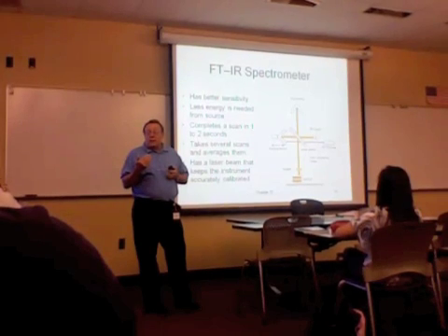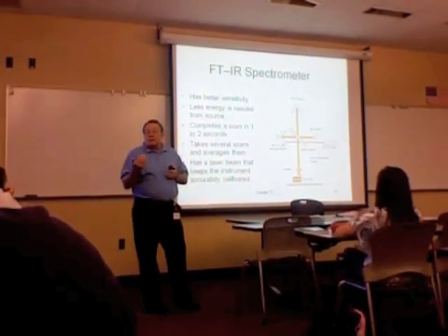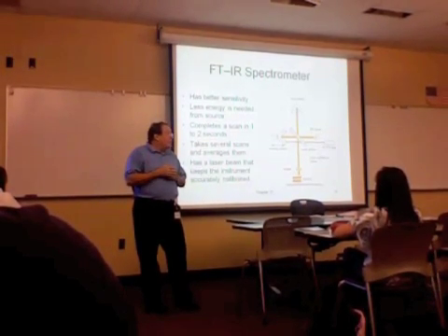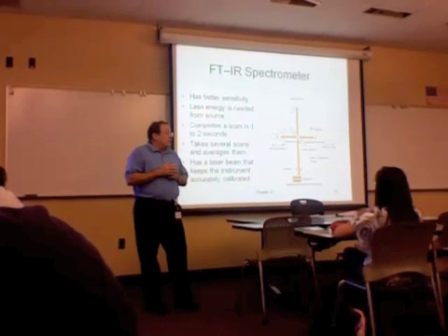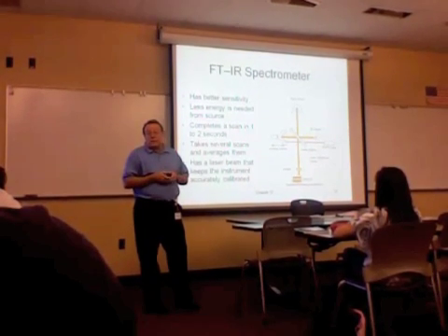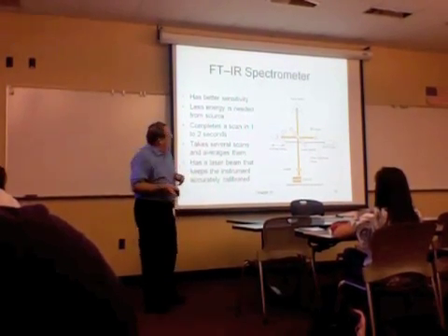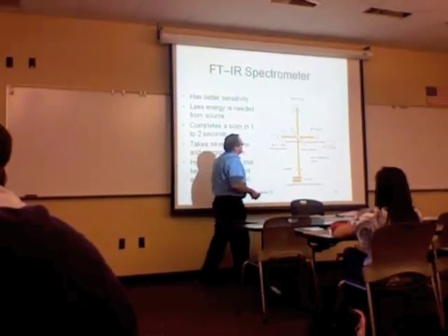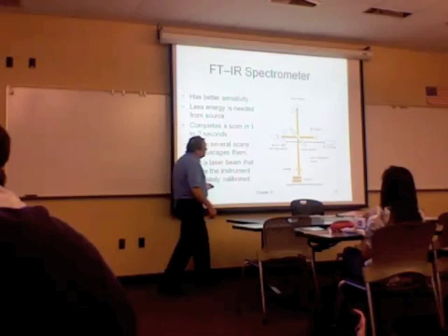And if the laser beam's intensity is beginning to fall off, that indicates that the instrument needs to adjust or rotate the angle of the mirrors and so forth until it optimizes. So it automatically calibrates itself. So we don't worry so much about the sensitivity of the optic path. This one's a little more sophisticated.